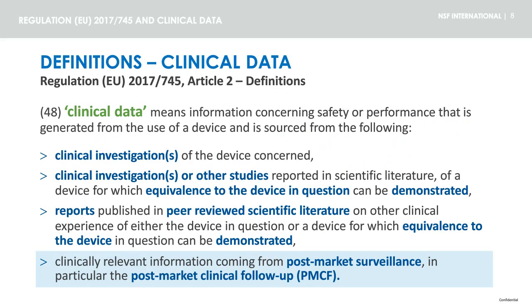So, what are clinical data? Let's go to Article 2, the definitions. Clinical data are data coming from clinical investigations of the device under evaluation, clinical investigations or other studies performed using equivalent devices, reports on other clinical experience of either the device under evaluation or its equivalent device, and clinically relevant information coming from post-market surveillance, in particular, the post-market clinical follow-up.